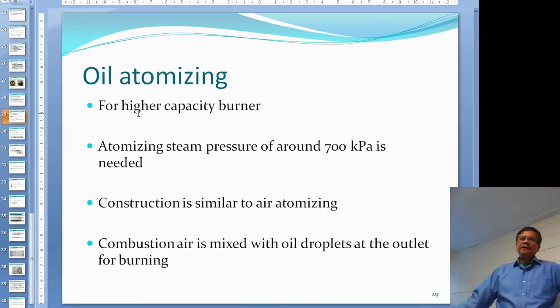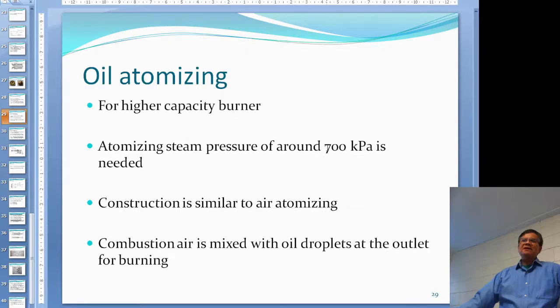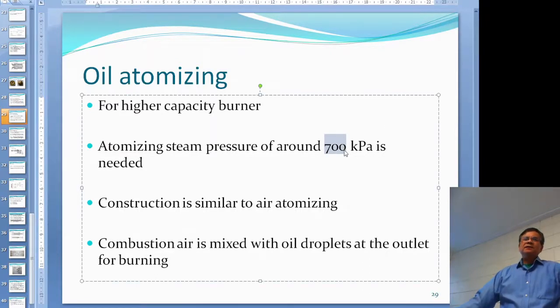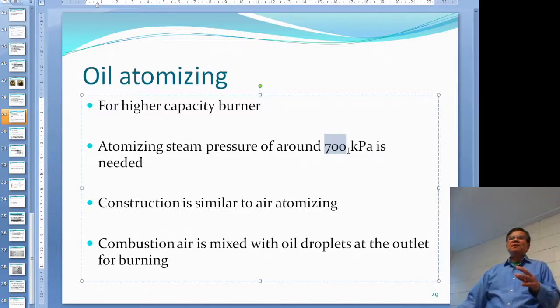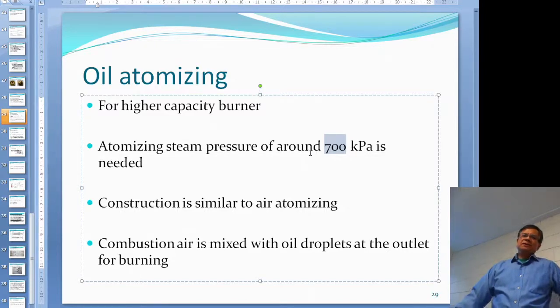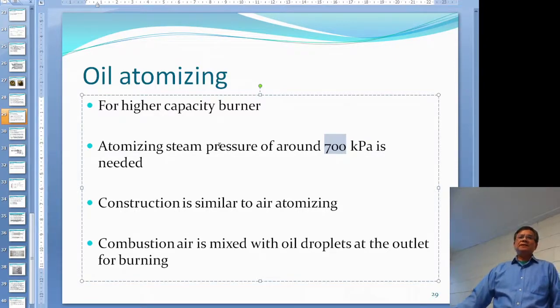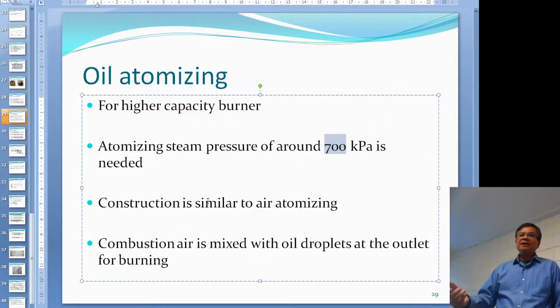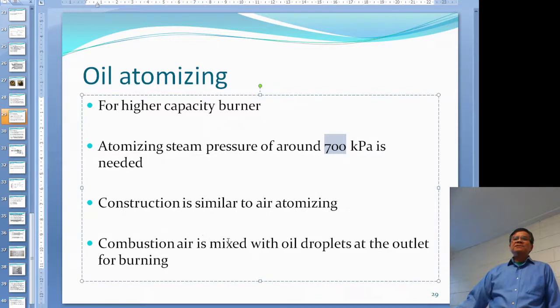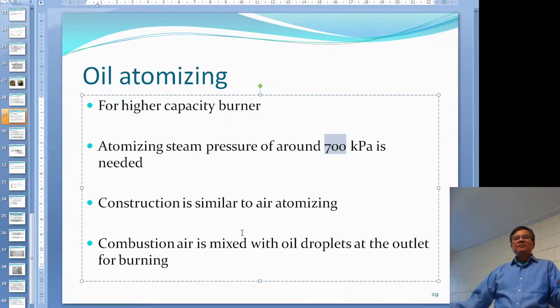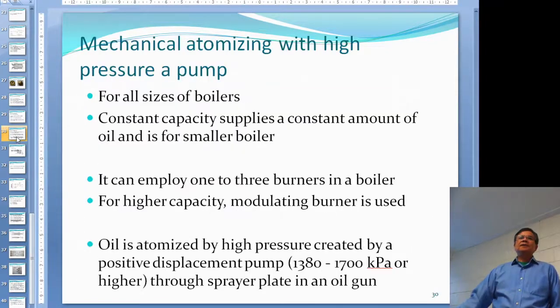For steam atomizing, it's used for higher capacity, larger boilers. The atomizing steam pressure is usually around 700 kPa — that's pretty much the minimum pressure. Many oil burning systems set the low atomizing steam cutoff around 650 kPa, because below that you really cannot properly atomize the oil. The construction is almost the same as air atomizing, but instead of air they use steam. The oil and steam are mixed in the same oil gun before being sent to the furnace.